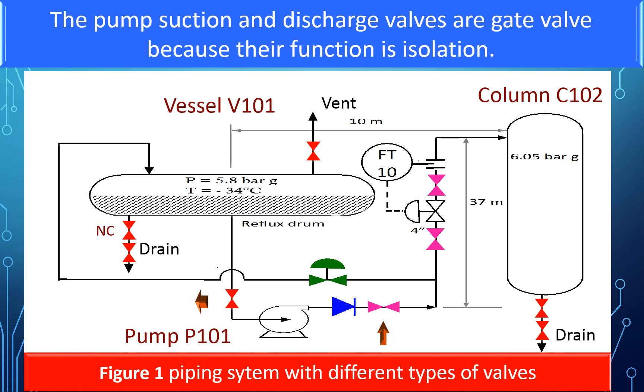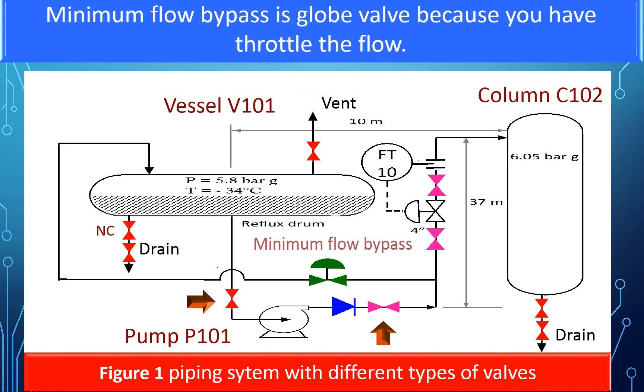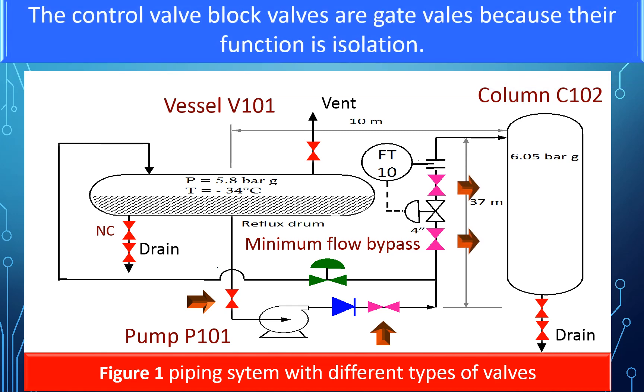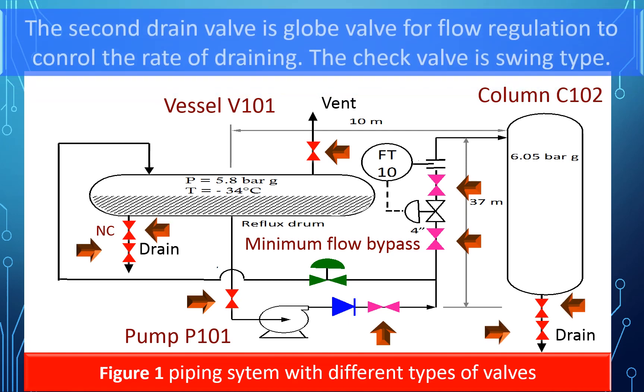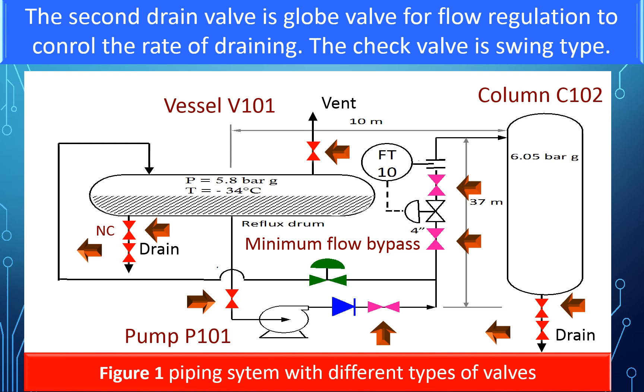The pump suction and discharge valves are gate valves because their function is isolation. The minimum flow bypass valve is a globe valve because you have to throttle the flow. The control valve block valves are gate valves because their function is isolation. Vent valves are gate valves because they are usually on or off. The first drain valve is a gate valve for isolation. The second drain valve is a globe valve for flow regulation to control the rate of draining. The check valve in the pump discharge is a swing type.